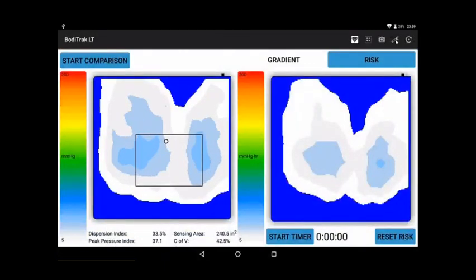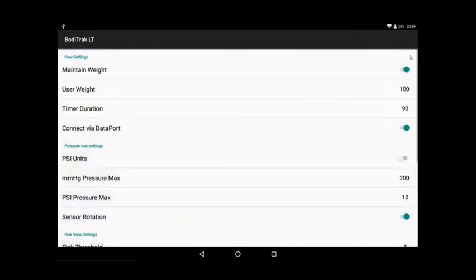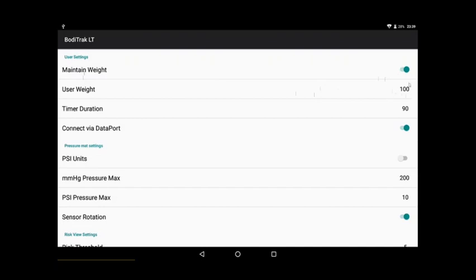Under settings you have maintain weight, which is used for longer term monitoring the patient in a wheelchair. It normalizes the force over time. It's required that you input weight to do that. The rule of thumb is usually 60% of the person's weight in the seated position.